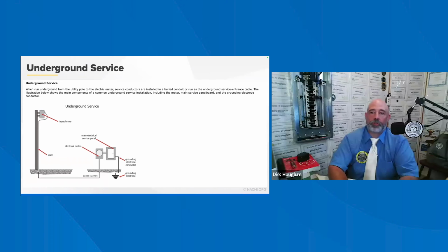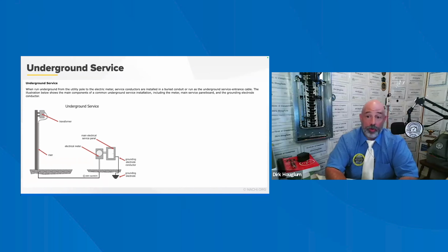The underground service conductors between the electrical supply system and the service point are called the service lateral. If the utility company has an underground supply system with transformers on pads at the property line, the service lateral is that which runs underground to the house from the transformer installed on the ground. If the electrical service is overhead, the homeowner may not want a service drop overhead line run across the property. In such cases, the conductors may be run down the utility pole in a raceway and then run underground to the house. Both of these installations would be called the service lateral, which is defined in Chapter 35 of the 2021 IRC, the Residential Code, as the conductors from the utility main pole at the point of connection and the service equipment or service entrance conductors at the house.